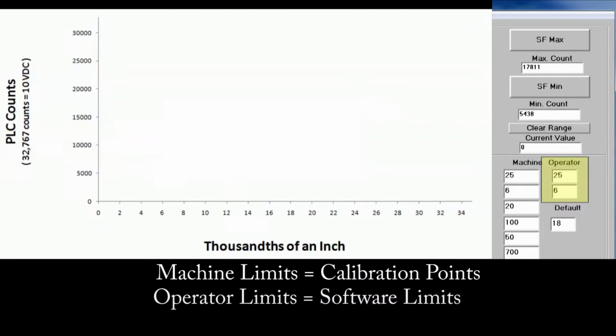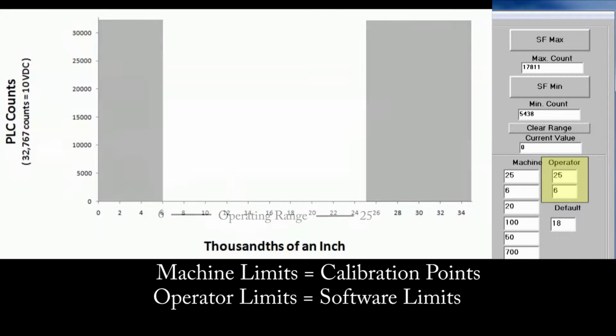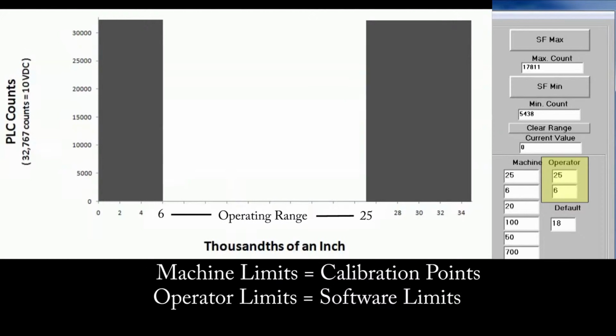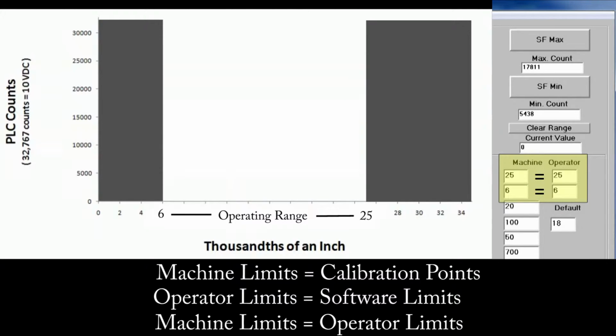The operator limits are not used for calibration, but are used to limit the range the operator can adjust the gap. The values entered limit the target gap values the operator can enter, as well as how much a gap speed curve can add or subtract from the target gap value. Typically, the operator limits should be set the same as the machine calibration limits you choose.